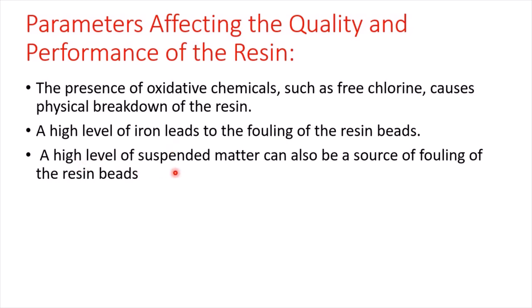A high level of suspended matter can also be a source of fouling of the resin beads. Here the solution can be a simple sand filter, or if the water is highly turbid, we can use coagulation, flocculation, and then sedimentation, depending on the amount of suspended matter in the water.